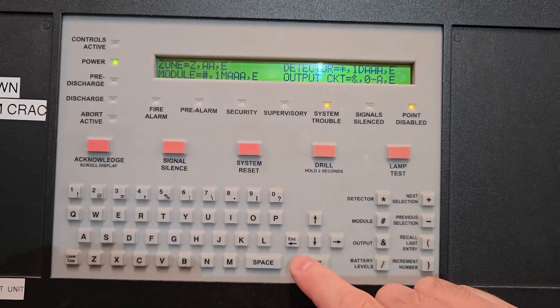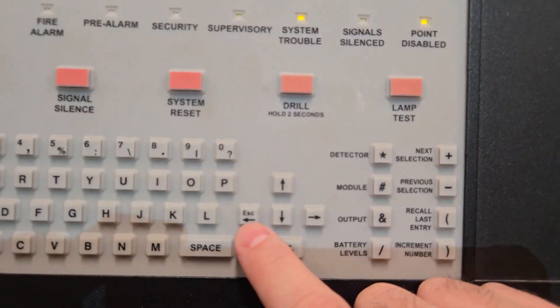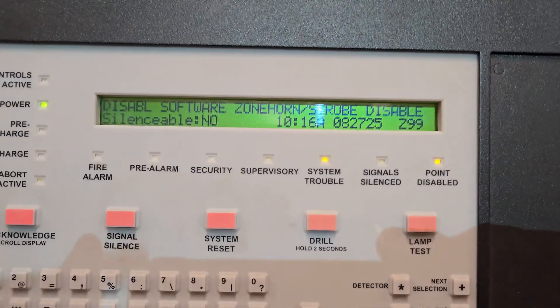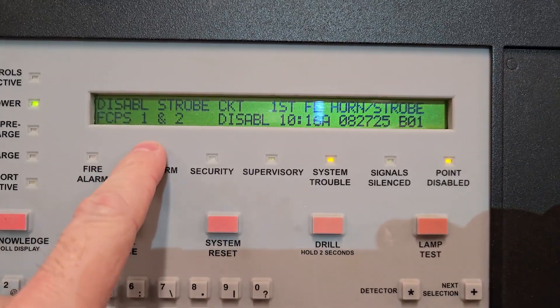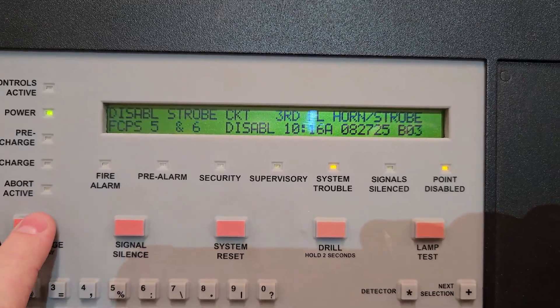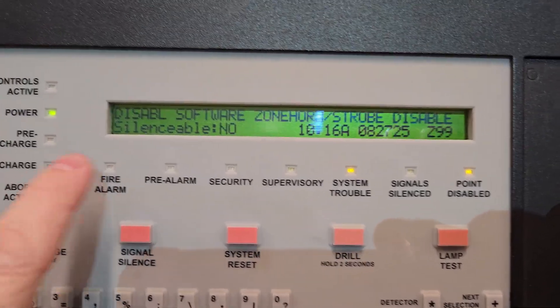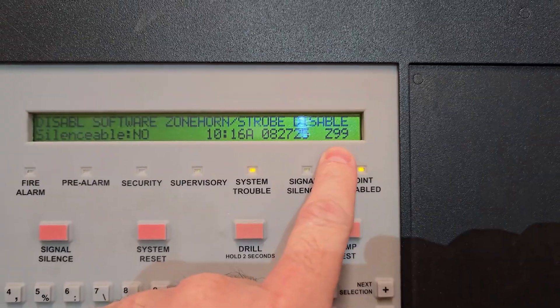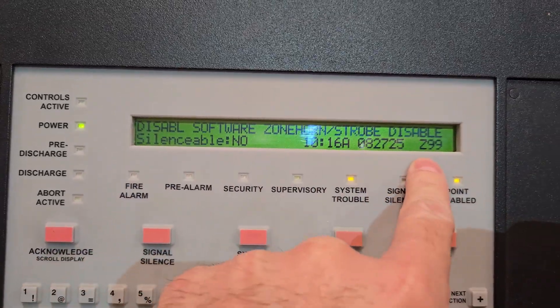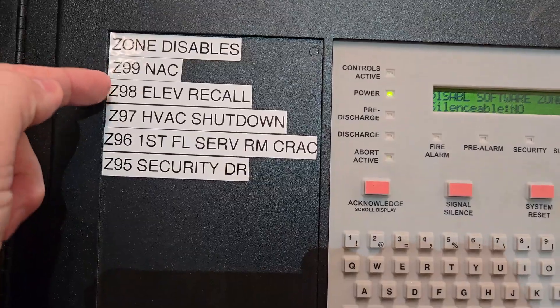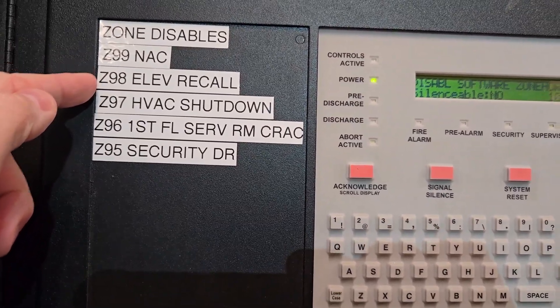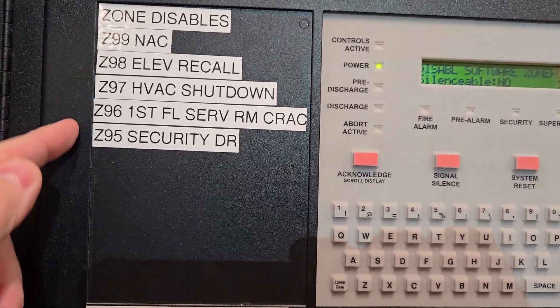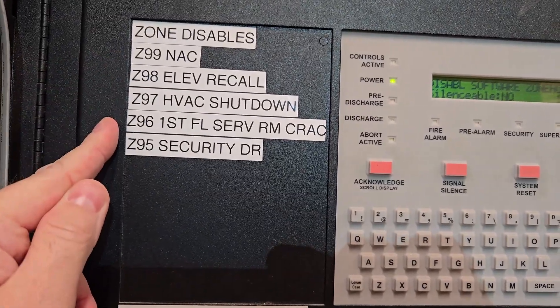I hit Enter and then I'm going to back out using the Escape button to go all the way back to the front panel. Now you can see it shows 'disable software zone — horn/strobe — disable zone 99.' So I've successfully disabled zone 99. I could also do the same process to disable the elevator recall, HVAC, server room, or security door zones.